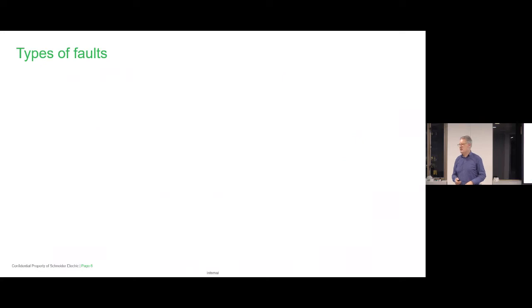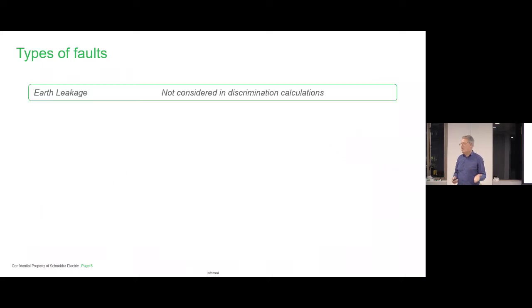So the first thing you need to consider is what sort of faults you are going to deal with. Not all projects are the same, but you typically will have overcurrent and short circuit. Let's just have a look at what those faults could be. There can be earth leakage. I'm not going to look at this in this case.